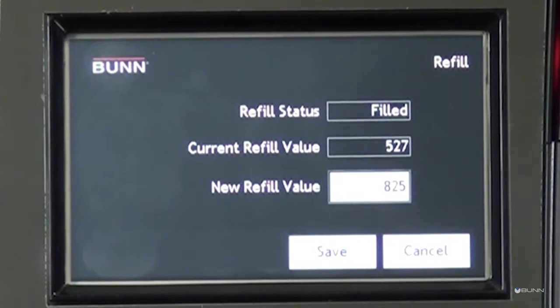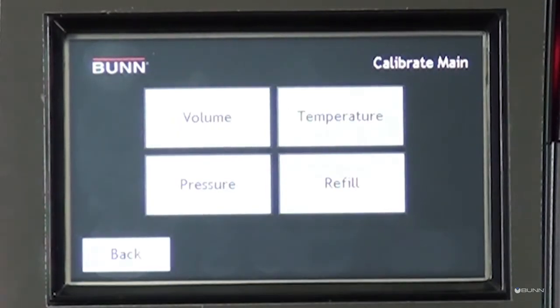Adjust sensitivity of refill probe according to water quality. Always make sure that the status is filled. New refill value should always be higher than current refill value when water is contacting the tank refill probe. Press Save when finished.